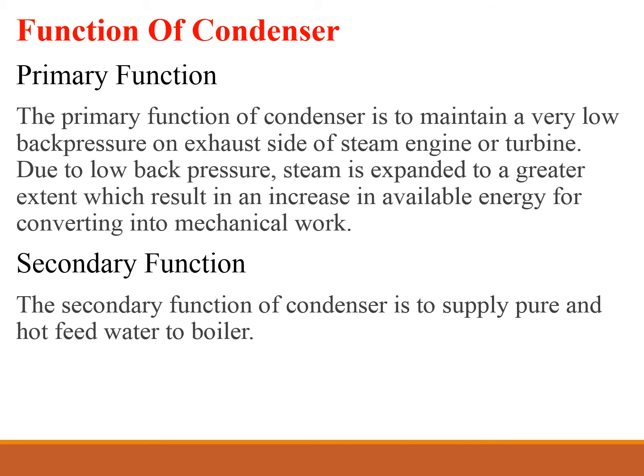Function of condenser. Primary function. The primary function of the condenser is to maintain a very low back pressure on the exhaust side of the steam turbine, which increases expansion of steam to a greater extent and also increases available energy for converting into mechanical work. Secondary function. The secondary function of the condenser is to supply pure and hot feed water to the steam boiler, which increases thermal efficiency of the steam power plant without increasing size.